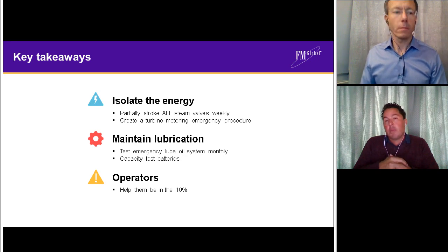So there is some scope to use condition-based monitoring, but from a time perspective, and especially on modern equipment, the sorts of testing that we're recommending at the frequencies that we are, the feedback from our clients is that if the equipment is appropriately designed, it's not overly intrusive to achieve those frequencies on the testing. And then again, the maintenance really falls within outage scope by and large, and so those frequencies tend to align.